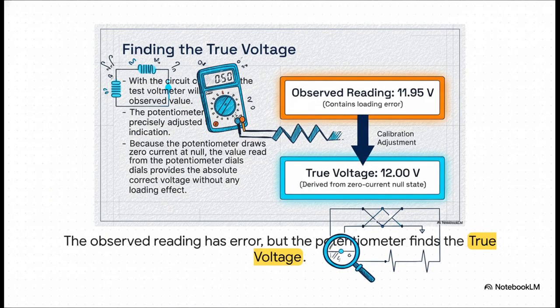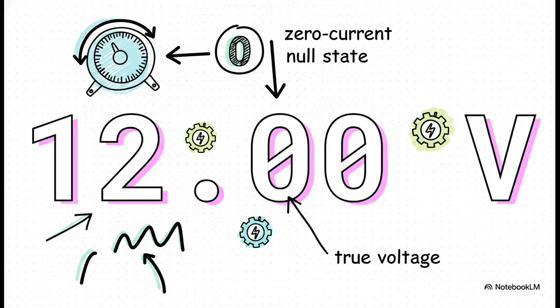And here is where we get the payoff. We hook up the voltmeter we want to calibrate, and it gives us a reading, let's say 11.95 volts. But we know better, right? We know that reading has been tainted by that loading error we talked about earlier. But then we bring in the potentiometer. We adjust the dials, we hunt for that zero current null state, and it reveals the true voltage completely free from any loading error, exactly 12.00 volts.